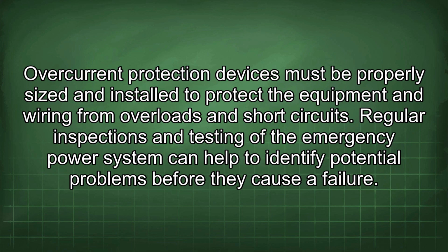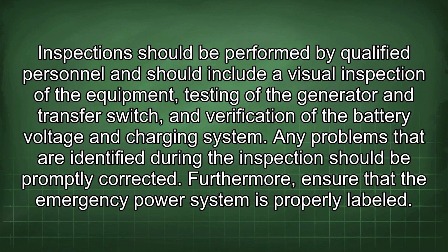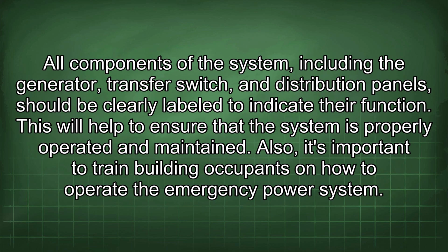Regular inspections and testing of the emergency power system can help to identify potential problems before they cause a failure. Inspections should be performed by qualified personnel and should include a visual inspection of the equipment, testing of the generator and transfer switch, and verification of the battery voltage and charging system. Any problems that are identified during the inspection should be promptly corrected. Furthermore, ensure that the emergency power system is properly labeled. All components of the system, including the generator, transfer switch, and distribution panels, should be clearly labeled to indicate their function. This will help to ensure that the system is properly operated and maintained.